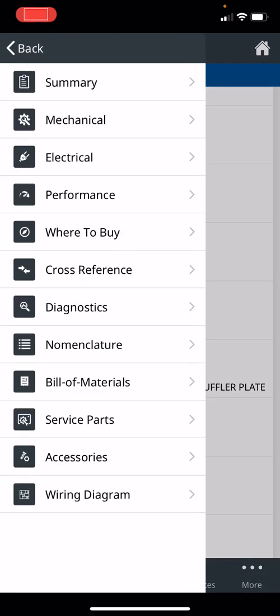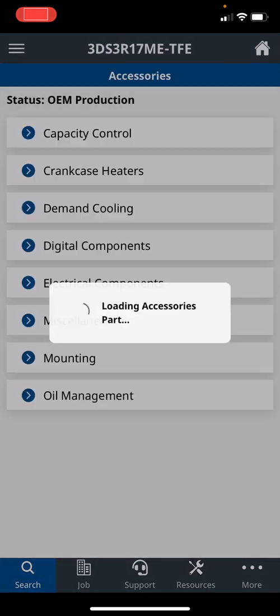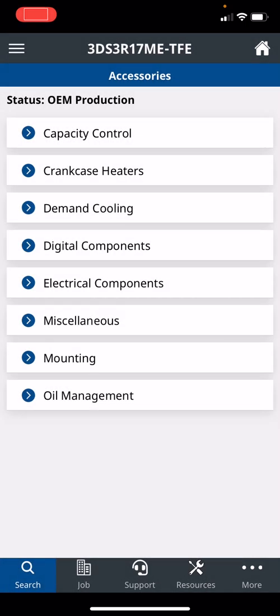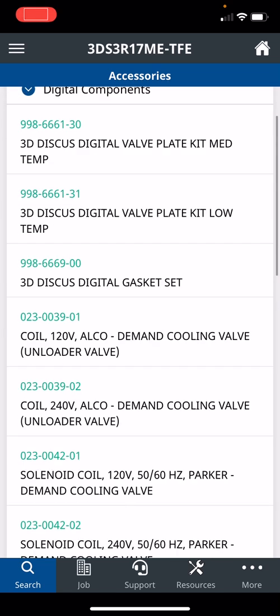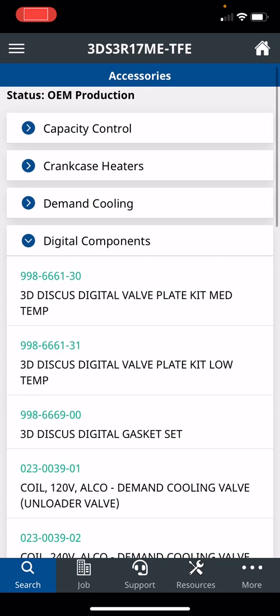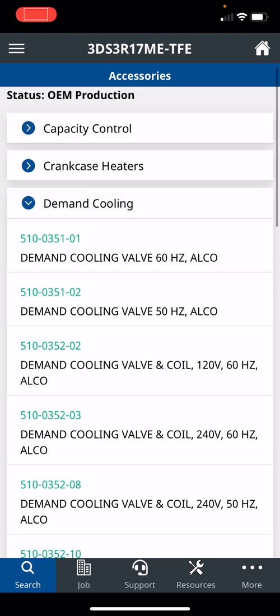From here, there's accessories. So if you need capacity control, if you want to add digital compressor onto that fixed compressor, you can just click on it. Here's the kit, 3D Discus Digital Valve Plate Kit, so you can retrofit that fixed compressor to a digital. Here's the part numbers. Demand cooling - I mentioned that these new blended refrigerants run a lot hotter, so you may need demand cooling if you're doing a retrofit job. Very helpful.